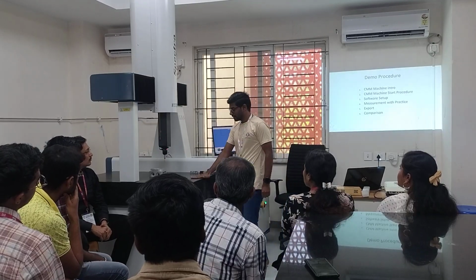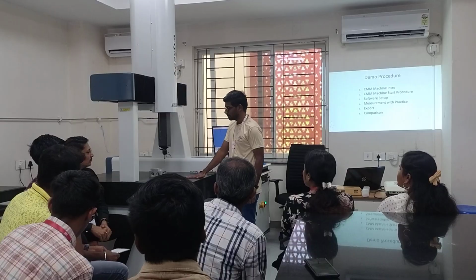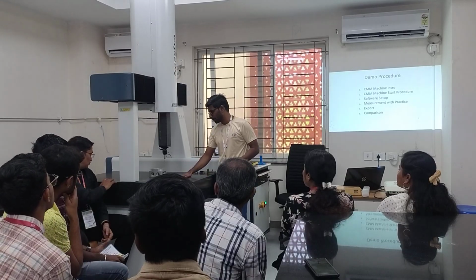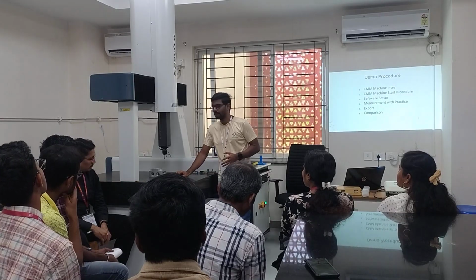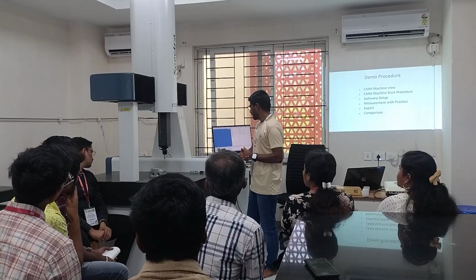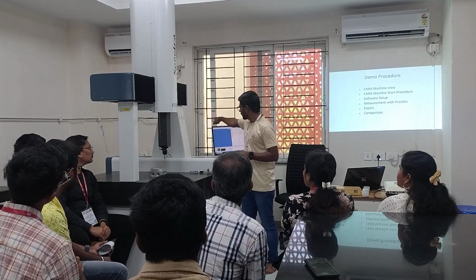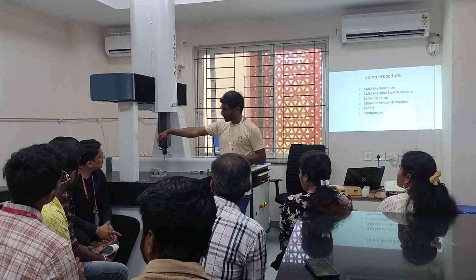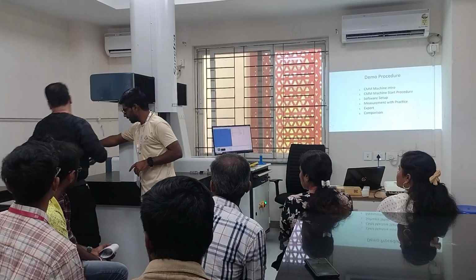This is called the surface table, where we place our parts. We have to make sure that rough metal surfaces are not placed here, because whenever we put plates or heavy objects on this, it gets scratched. So the surface table has to be maintained. The basic parts of this: we are getting a pressure line. The pressure coming from there is around 6 bars. But behind, sir, can you please check and tell me how much is the pressure behind? Here.